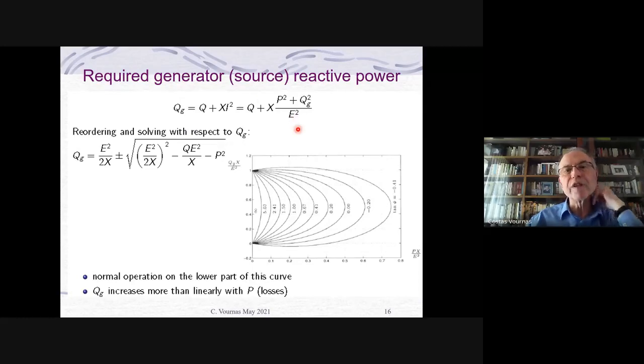So to do this, I want to compute from the AC system the Q generated by the source, which is the Q of the load, plus what we call the reactive losses, X I squared. And these are written again as a function of P and QG and E, which is a constant voltage. You see I get an equation here, which I can solve for QG. And you have this solution here, which you can have for different power factors again, because Q can be, if you have Q equal tangent phi times P, you get a simple one.